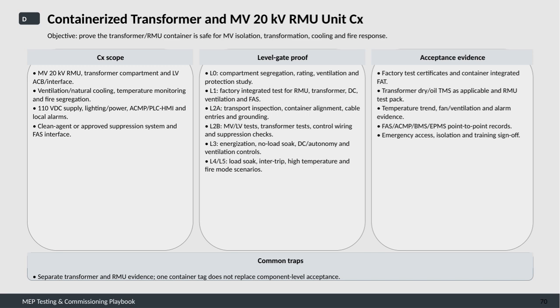Lastly, a common pitfall to watch out for is the assumption that one container-level acceptance tag is sufficient. It's important to maintain separate acceptance evidence for both the transformer and the RMU components, as a container tag does not replace detailed component-level acceptance. This ensures thorough verification and reliable commissioning of the entire unit.